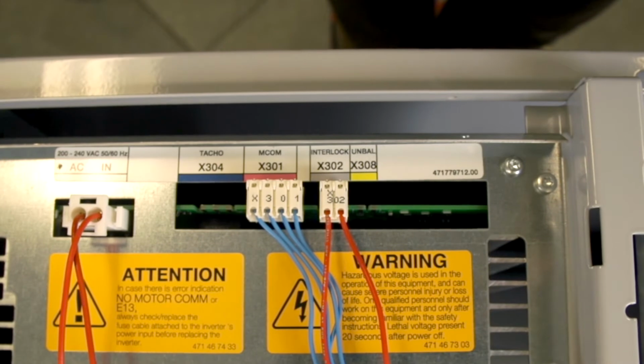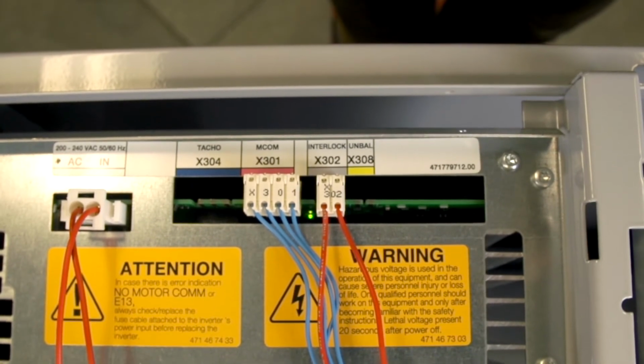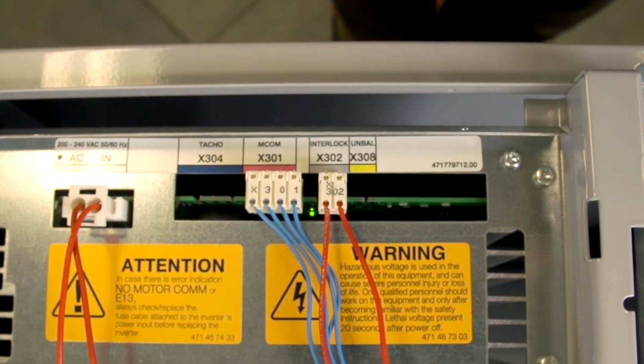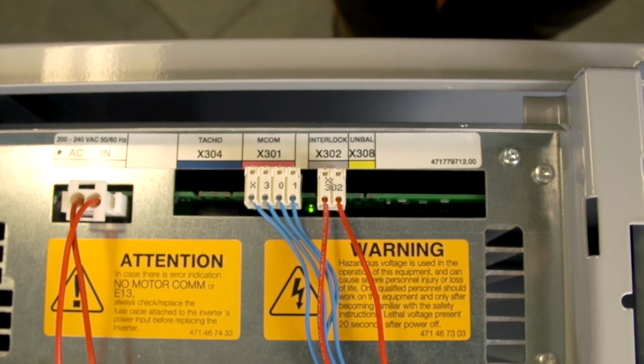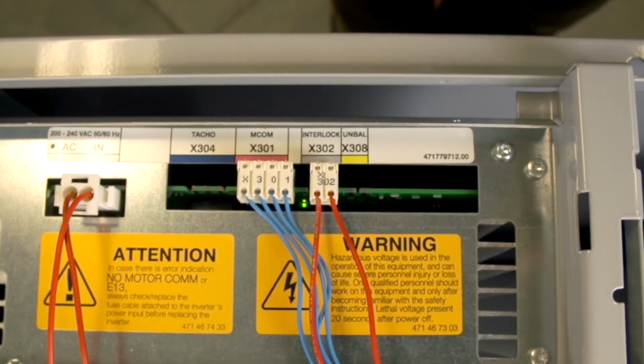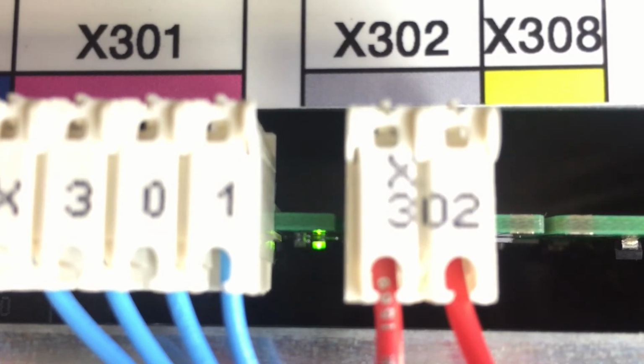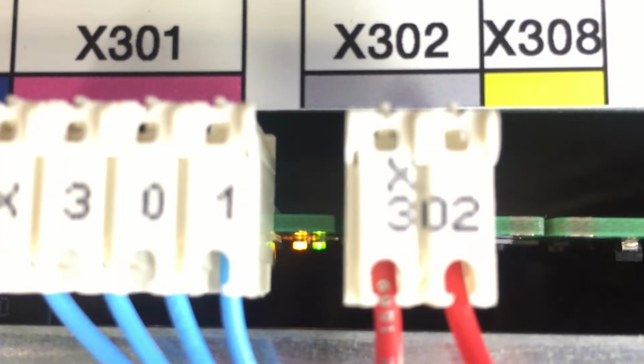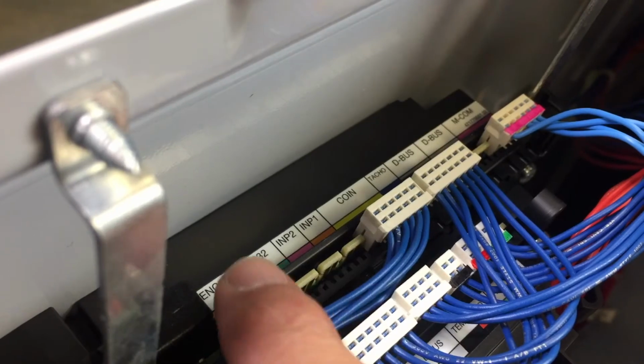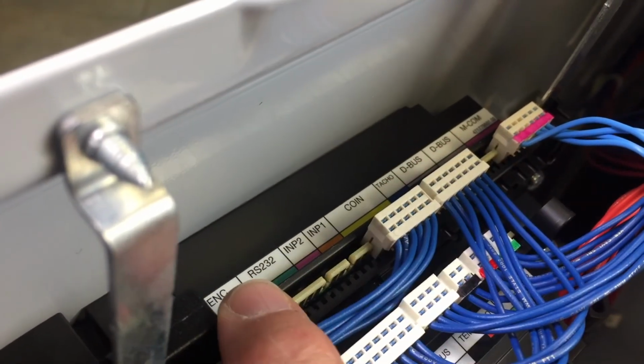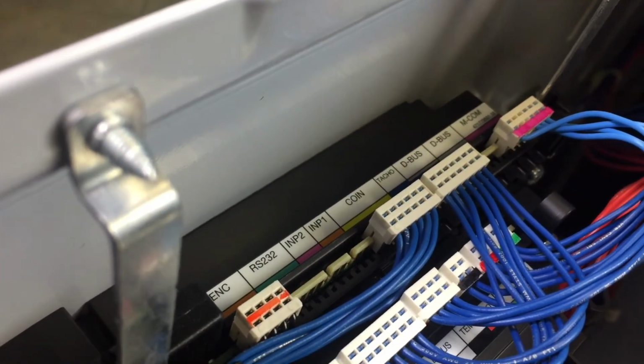If the LED is lit and blinking off momentarily once every 5 seconds, it indicates that there is power to the MCU and that the control electronics in the MCU are functioning. If the LED is not blinking as described, trace the fault in the voltage feed to the MCU PCB as described in the service manual for the relevant machine.